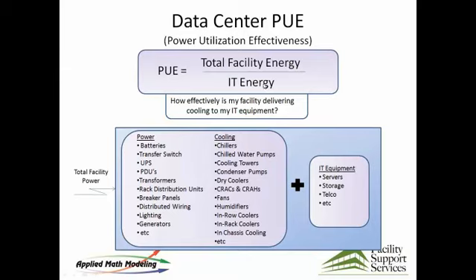All right. So what were you thinking? Take us through your thought process here with respect to improvement. Well, what we did when we went in, we took a baseline of what the CRAC operation was. We took supply and return temperatures. We took amp readings. We took static pressure readings. And we took all CFM readings. And then we compare that to what the CFD shows us. And the immediate result was trying to block off that underfloor plenum from the NOC to the data center. So we would like to optimize their existing conditions for the most cost savings, and they really need to define improvements, and they will see widespread change.